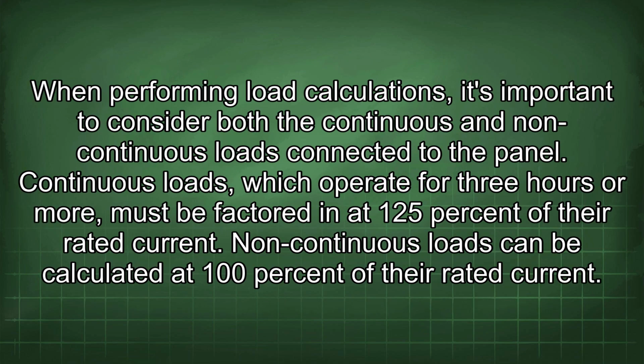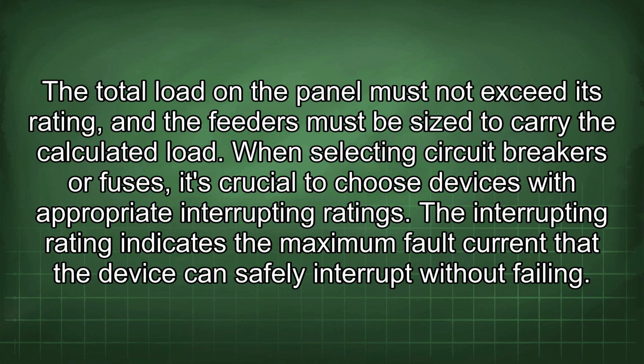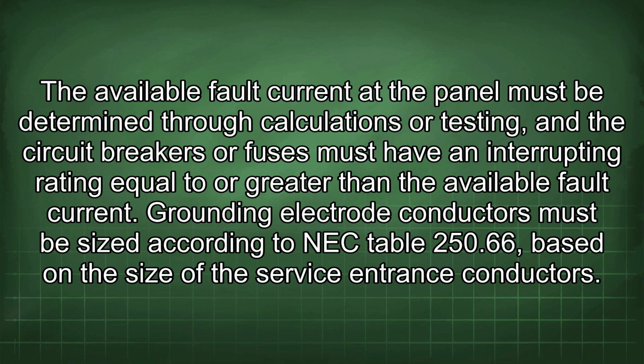When performing load calculations, it's important to consider both the continuous and non-continuous loads connected to the panel. Continuous loads, which operate for 3 hours or more, must be factored in at 125% of the rated current. Non-continuous loads can be calculated at 100% of their rated current. The total load on the panel must not exceed its rating, and the feeders must be sized to carry the calculated load. When selecting circuit breakers or fuses, it's crucial to choose devices with appropriate interrupting ratings. The interrupting rating indicates the maximum fault current that the device can safely interrupt without failing. The available fault current of the panel must be determined through calculations or testing, and the circuit breakers or fuses must have an interrupting rating equal to or greater than the available fault current.